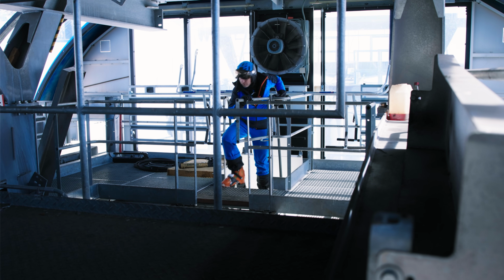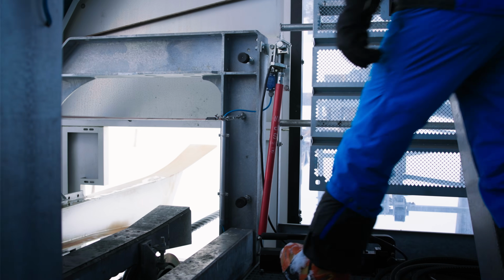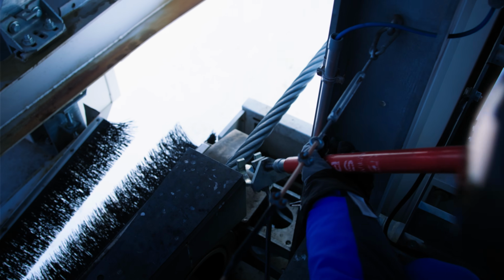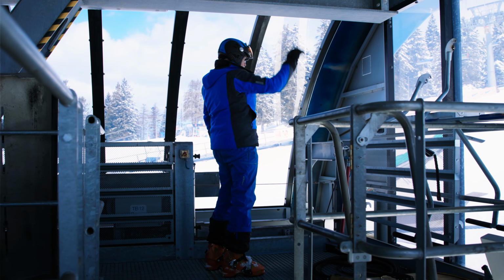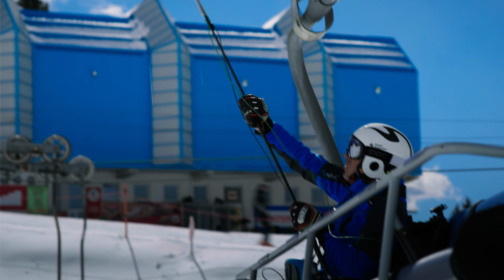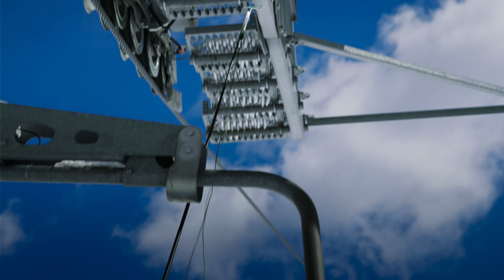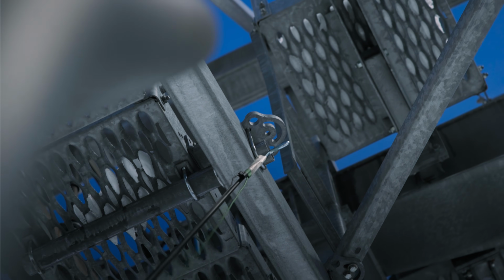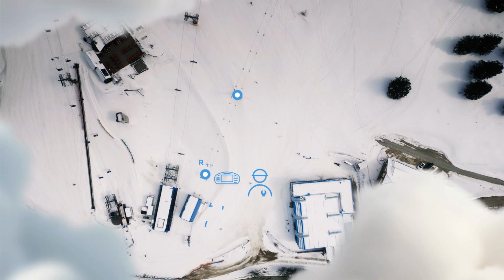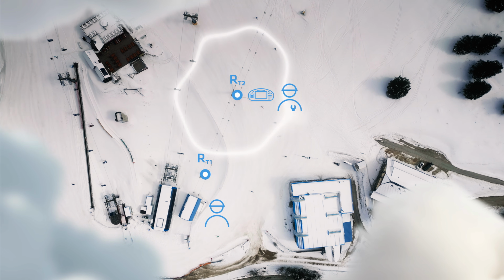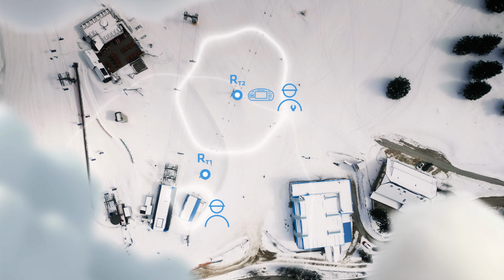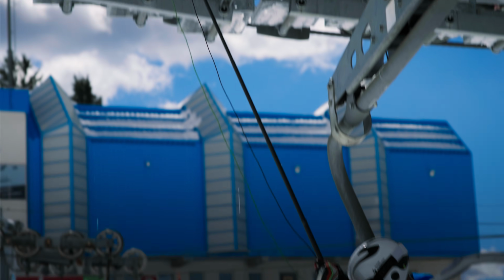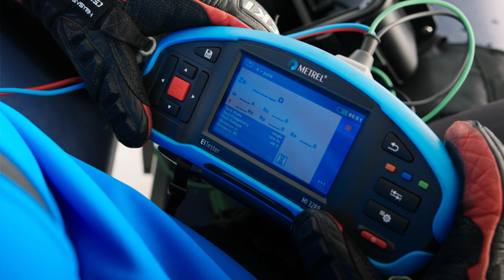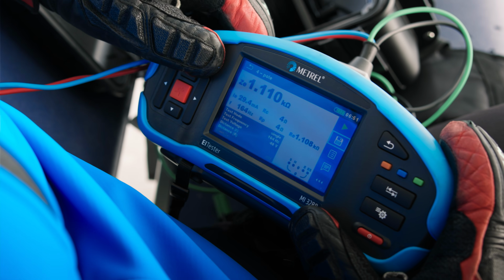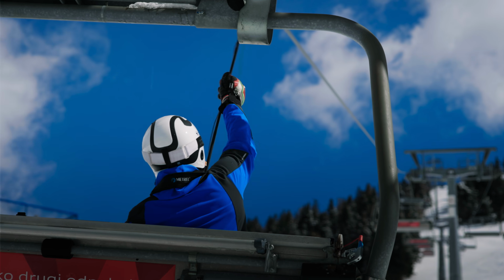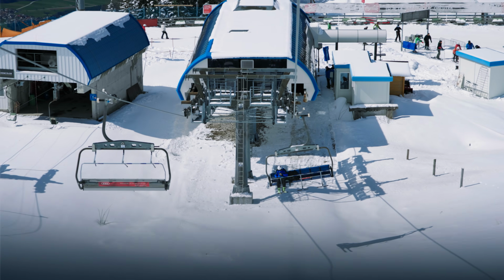At each stop, the operator grounds the carrying cable at the lower station, unless it is already grounded during operation, which saves time. The inspector connects to the conductive part of the tower using a dedicated adapter and performs a 4-pole earth test. The MI3288 generates the test signal and accurately measures the grounding resistance. Expected results for tower grounding are typically within the ohm range. When resistance reaches 1.1 kiloohms, as in our case, the tower requires immediate repair or reconnection to the earthing system.